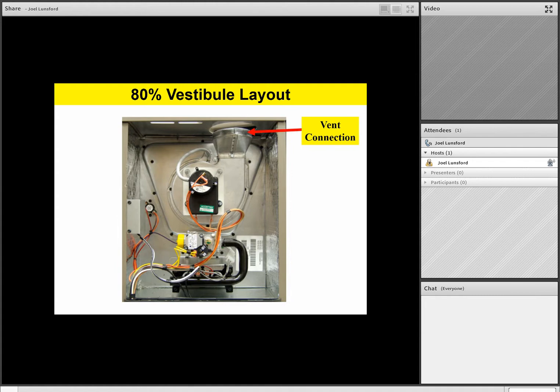So the first thing we're going to notice in the upper right hand corner, we have a vent connection. You'll notice this vent connection is a metal vent connection, and that's correct for an 80% furnace. You will have to use the appropriate venting material for a metal vent. The induced blower housing, this is where the induced draft blower, the housing itself is also made of metal, and then mounted right on the induced draft blower housing is our pressure switch. Now remember, team, this pressure switch has to be open electrically during an initial call for heat. And we'll talk a little bit more about that when we get into sequence of operation.